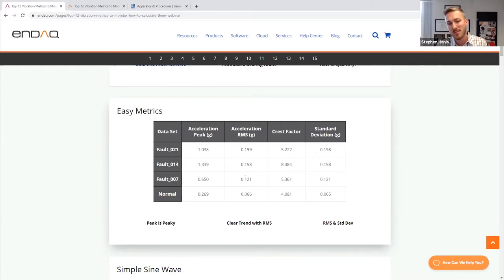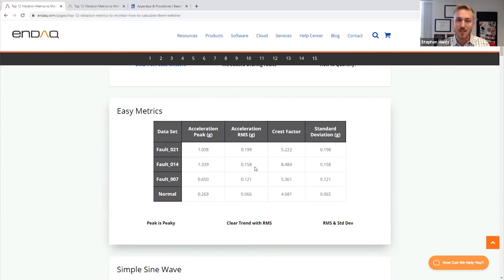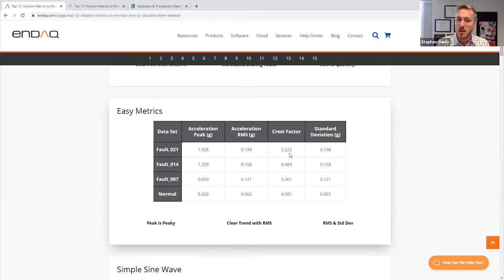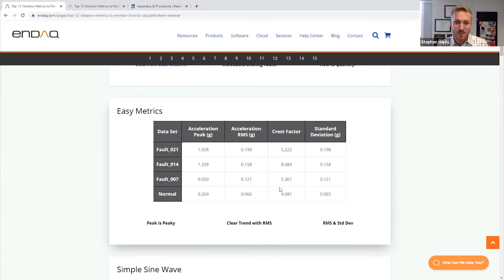Now let's look at acceleration RMS — kind of my favorite metric, combined with standard deviation. Acceleration RMS has a clear trend: as there's a fault condition, it has a higher RMS, and as that fault gets worse, the RMS increases. This looks like a pretty good indicator of bearing health and the energy in a vibration profile. Then there's crest factor, which is a unitless metric — it's just dividing the peak by the RMS value, defining how peaky your signal is. Crest factor is a great thing to monitor, but it's not a perfect trend here, so be careful if you just look at crest factor of a single file. You have to take a moving average of crest factor as well.